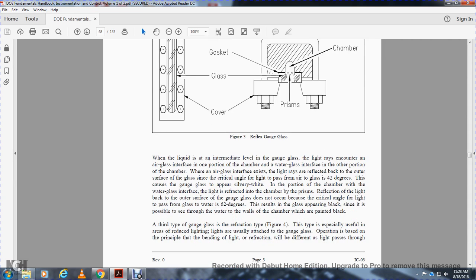With liquid at an intermediate level within the gauge glass, the light rays interfere with one portion of the chamber with the air, and with the other portion of the chamber with the water. In the air portion, the light waves reflect back to the outer surface of the glass, since the critical angle for light passing from the glass to air is 42 degrees, so that portion of the gauge appears white. In the water portion, reflection of the light back to the outer surface of the gauge glass does not occur, because the critical angle for the light's path from glass to water is 62 degrees. The result is that the glass appears black, and since it is possible to see through the water, the wall of the chamber will be painted black.